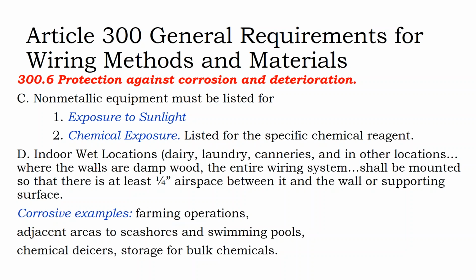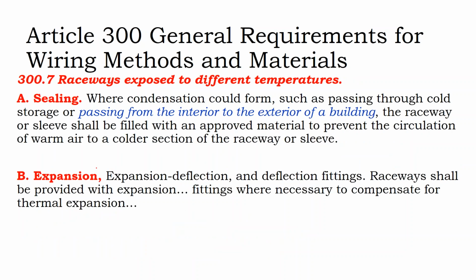Non-metallic equipment must be listed for exposure to sunlight. Now, you get a different electrician's conduit than you do for a plumber's PVC conduit. Plumbing, you know, that's where the sun don't shine. You don't need to worry about plumbing conduit exposed to sunlight. Electricians would. But then again, there are other corrosive environments beyond, I don't know, a chicken farm. A swimming pool may be a corrosive environment. You seal your raceways whenever you pass from the interior to the exterior of the building.